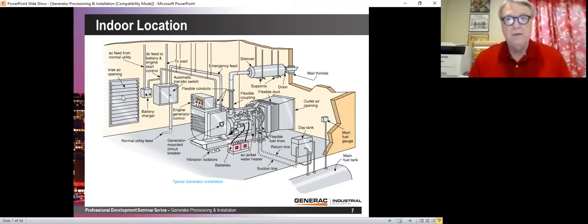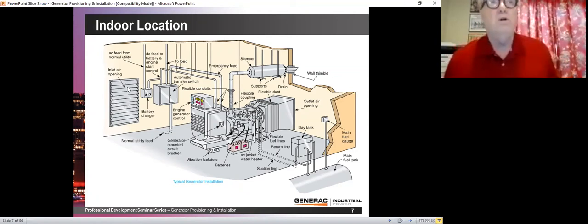I understand this is just a drawing and I'm being picky, but I would say the inlet air opening is undersized, and this can be a common problem in generators, that you have an air restriction because the inlet air opening is too small. Now, typically, if the inlet opening is just open louvers, then what you're going to have is a cold building.